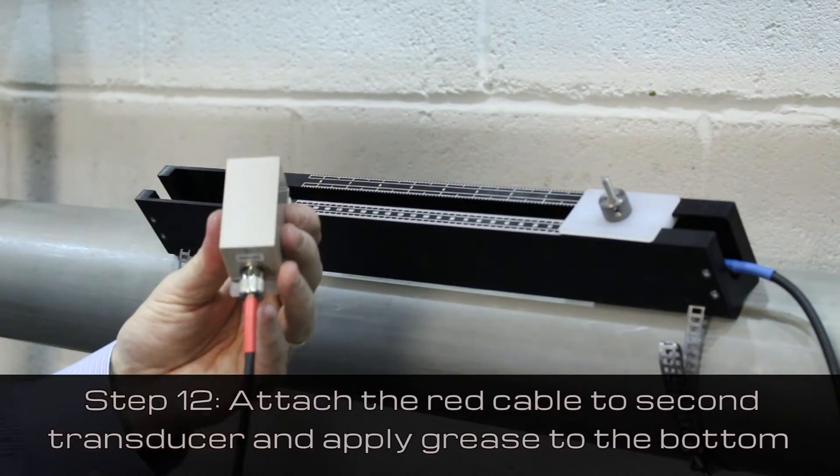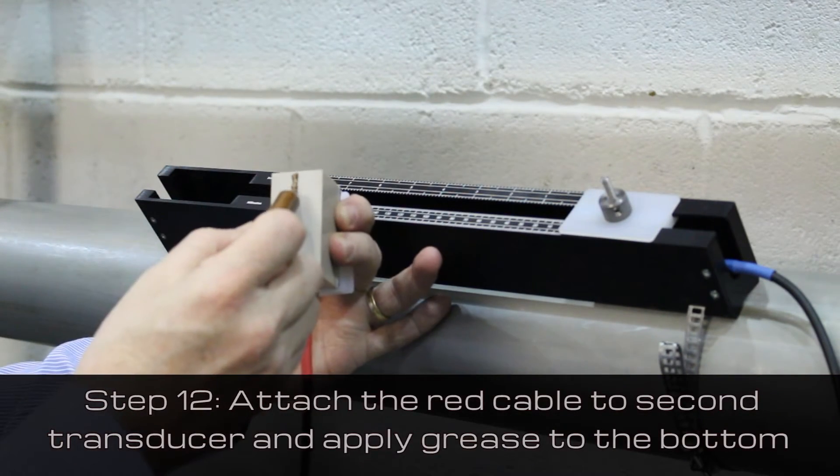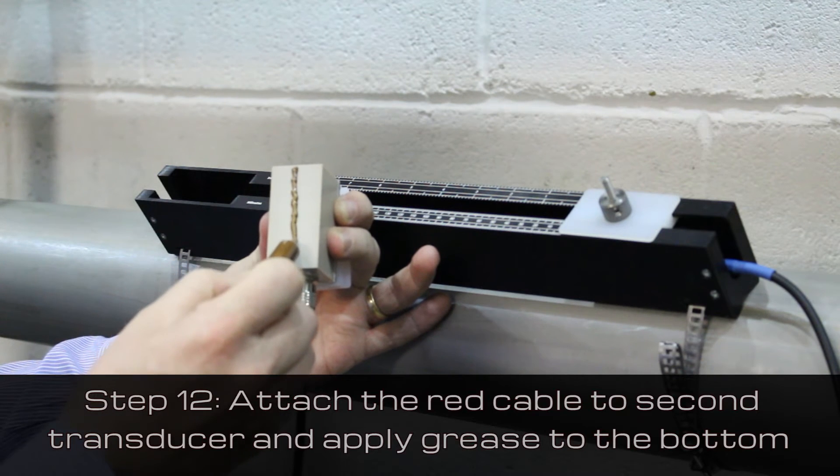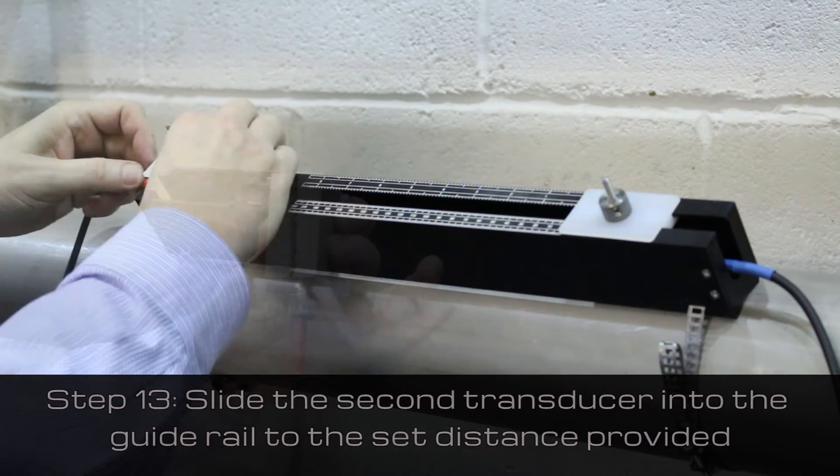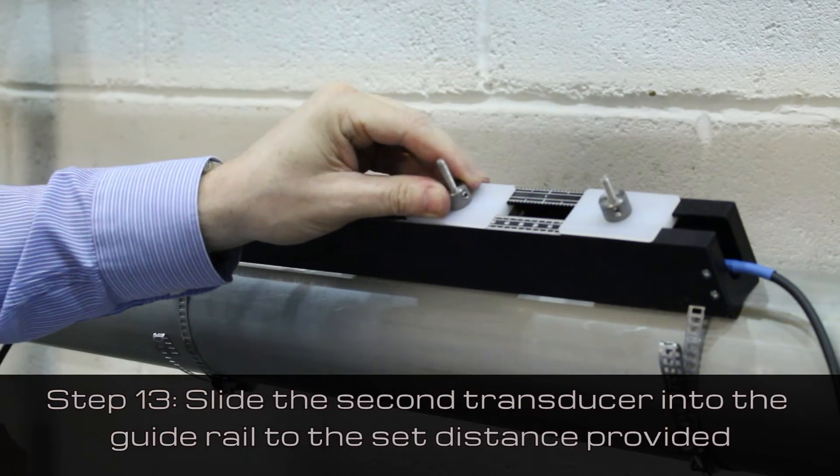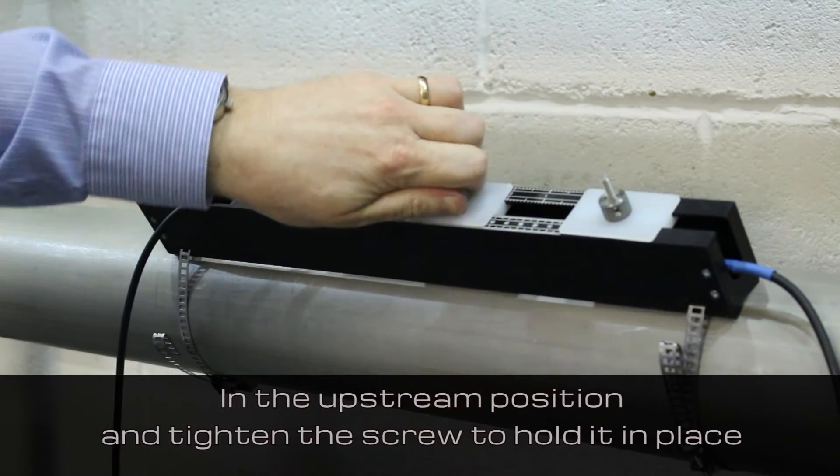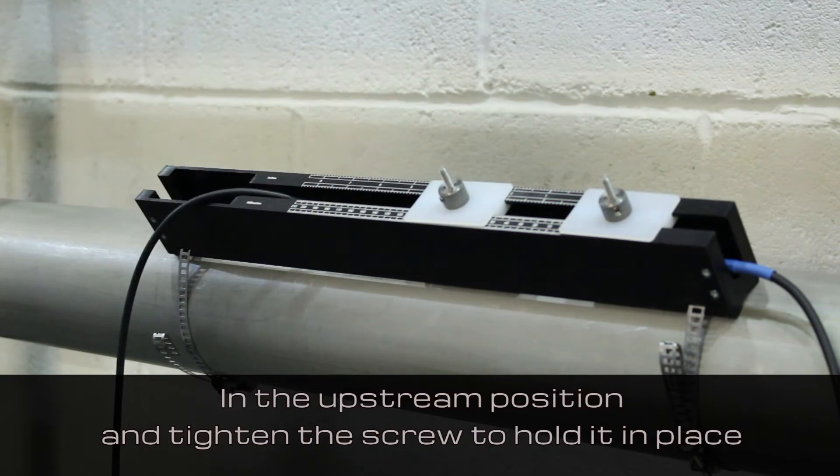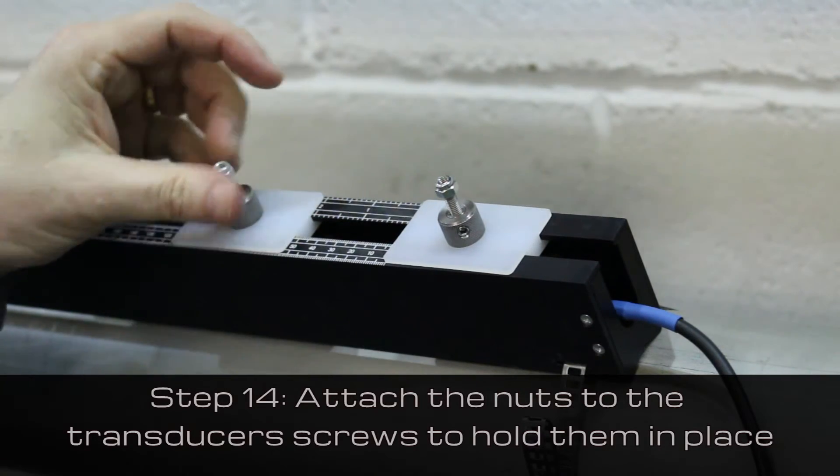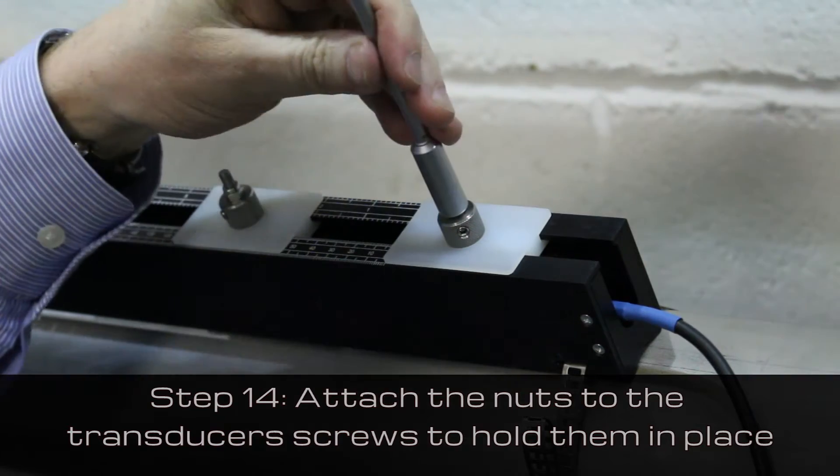Tighten the screw. Attach the red cable to the second transducer. Apply the grease and slide the transducer into the guide rail to the set distance provided by the flow meter in the upstream position. Tighten the screw. Attach the nuts to the transducer screws to hold them in place.